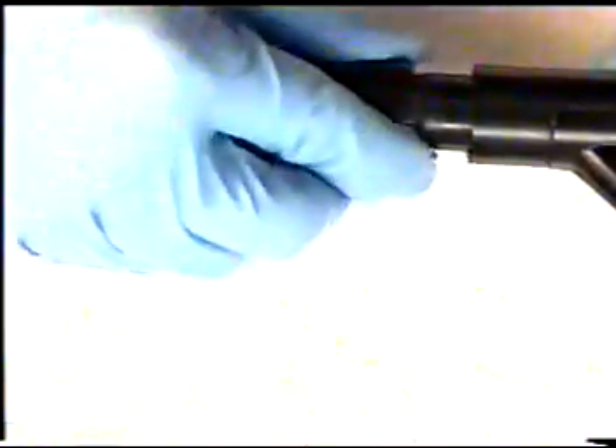Pull down cone to approximately 80 centimeters on the scope. If the cone or boot is very difficult to remove by hand, it may be necessary to use a pair of pliers with a soft rubber padding as not to scratch the boot cone. It may have to be removed in this fashion, again if it is too tight. Once the boot is loosened, again pull it down the insertion tube approximately 80 centimeters.